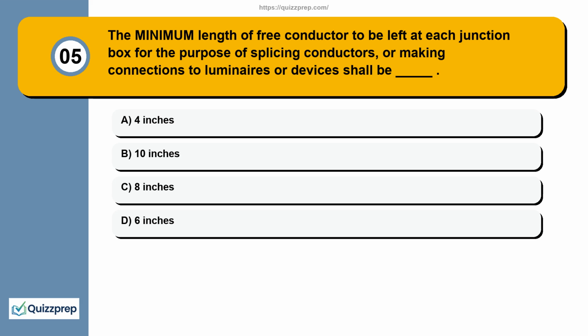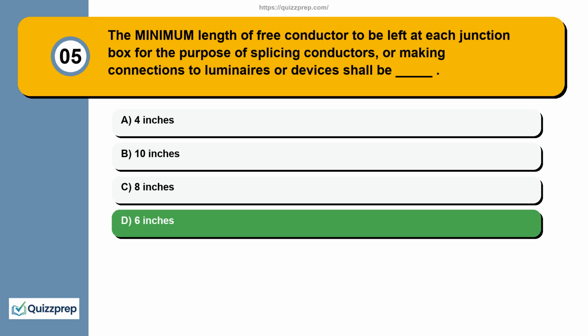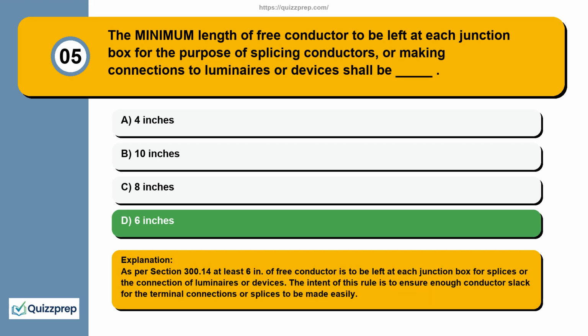Question 5. The minimum length of free conductor to be left at each junction box for the purpose of splicing conductors, or making connections to luminaires or devices shall be 4 inches, 10 inches, 8 inches, 6 inches. As per section 300.14, at least 6 inches of free conductor is to be left at each junction box for splices or the connection of luminaires or devices. The intent of this rule is to ensure enough conductor slack for the terminal connections or splices to be made easily.